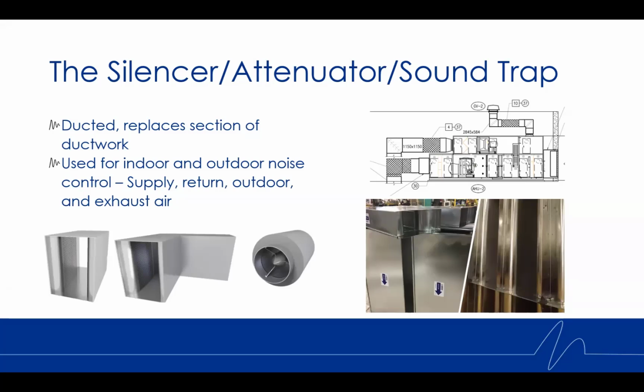So in the image top right, you can see the hatched sections are typically where the silencers are installed, generally closer to the unit to help mitigate that noise before it gets into an occupied space. We have a couple different configurations of these, so they can be rectangular or elbow shaped. We have circular ones to match circular ducts, and we can make custom sizes as well. You can see some examples of completed product on the bottom right-hand side there.